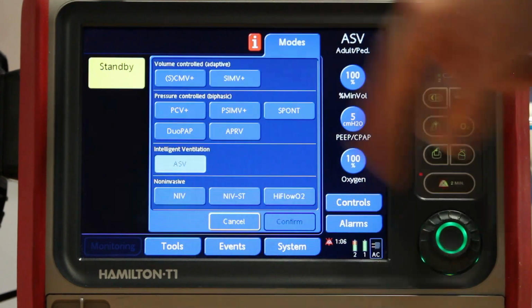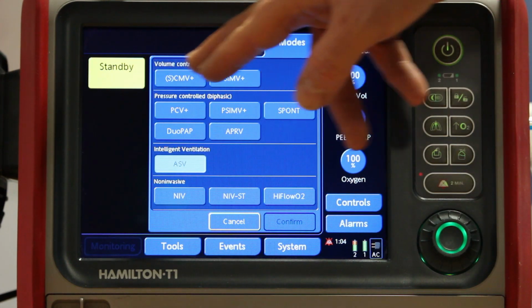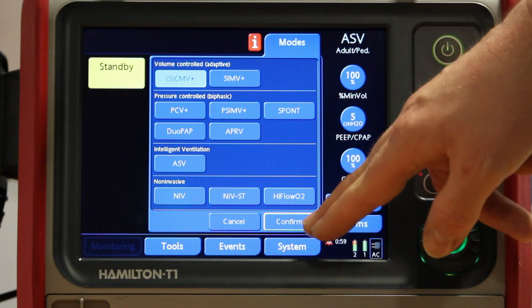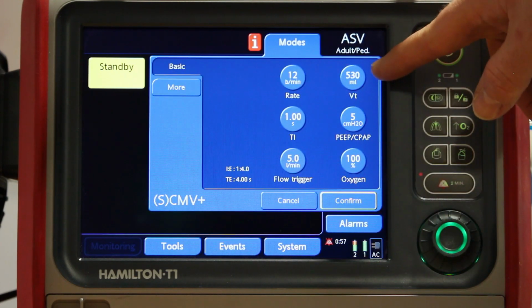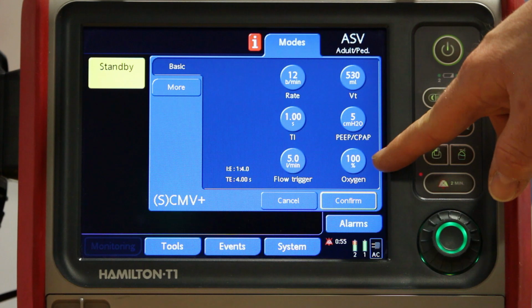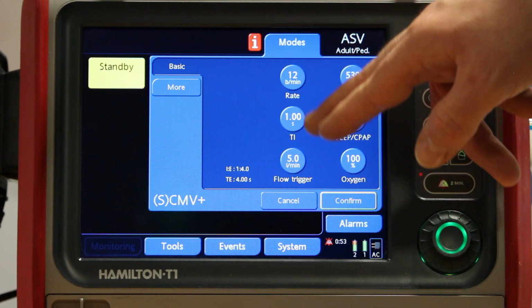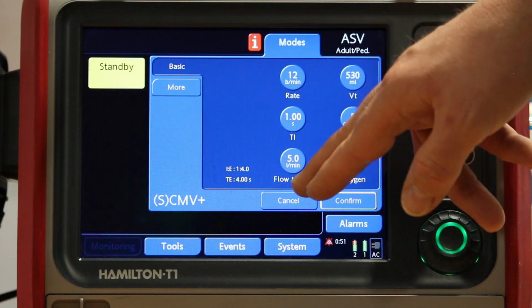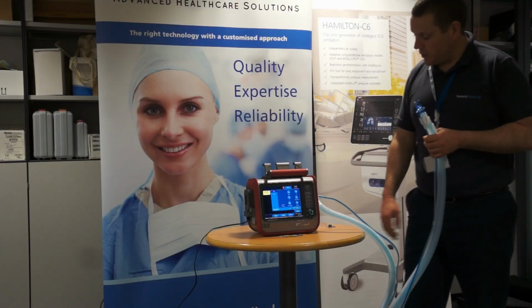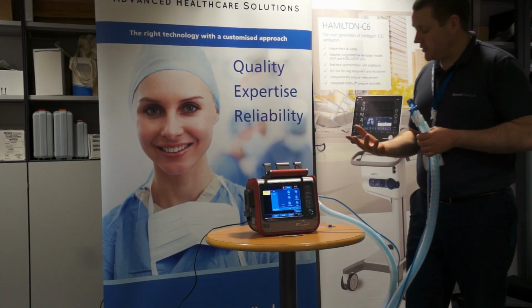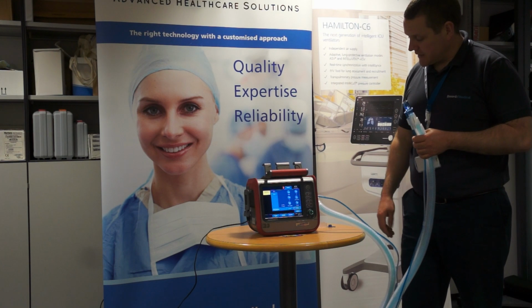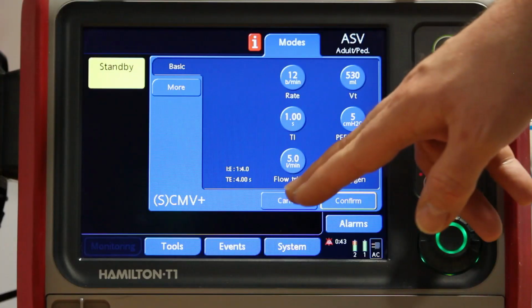So here let's look at the modes. We have 2 volume control modes up on top. We have controlled mechanical ventilation, which is our basic volume guarantee. So we're setting a tidal volume over PEEP with our FiO2, rate, I time and a flow trigger. There's no pressure support in the mode, so it won't support any patient triggered breaths, and there's a possibility of stacking depending on where the patient triggers in the cycle.